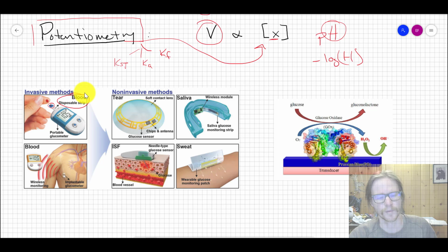So there are several other methods, like implementing these on contact lenses. These exist. These are electrochemical, so they do electrochemistry on your tears. Glucose is in your tears. Glucose is easy to oxidize, so you can grab an electron from glucose and then measure the current. The hard part is not doing the electrochemistry, it's transducing that to some device that can then measure it. So building a soft contact lens with interdigitated gold electrodes like this has been around for 20 years. The difficult part is miniaturizing the wireless transduction mechanism, but with 5G, etc., these things are now available.